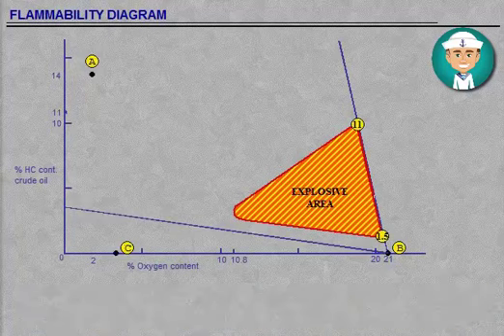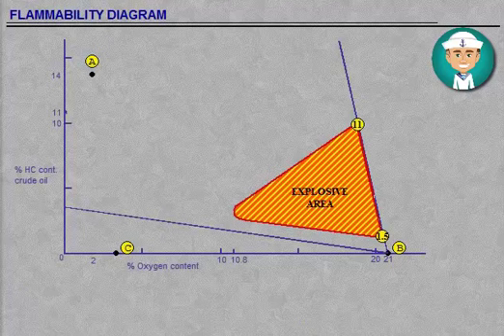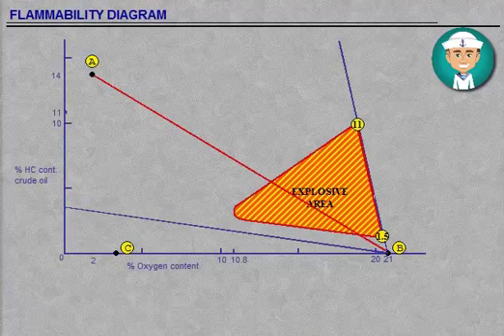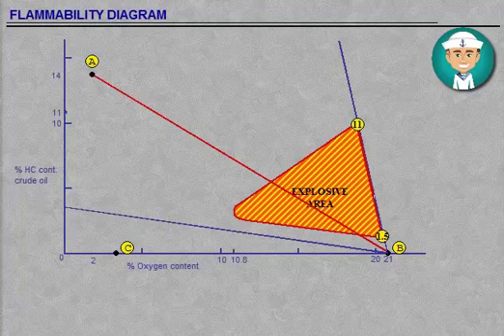If we start venting at point A with air, a line will extend from point A straight to point B through the flammable area. Avoid this at all costs.